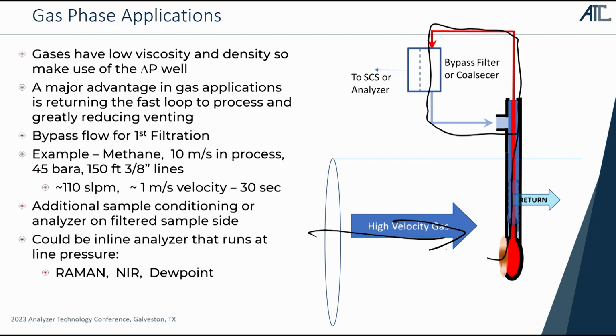And all of the flow gets returned to the process, even if it's at high pressure. So if we have a stream that has, say, H2S in it or methane we don't want to release, it lets us return back at pressure. In a typical example, if I've got about 10 meters per second of flow, which is a typical natural gas pipeline, and I put in 150 feet of 3/8 inch tubing to run my fast loop over, and I'm at 45 bar in that pipeline, typical natural gas pipeline, 600, 650 pounds, I'll drive through that loop at about a meter a second. So I get 30-second response time.